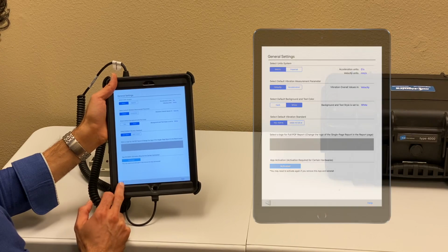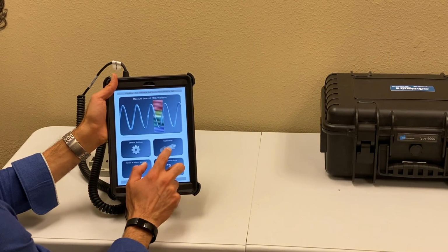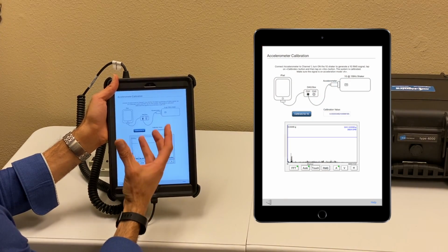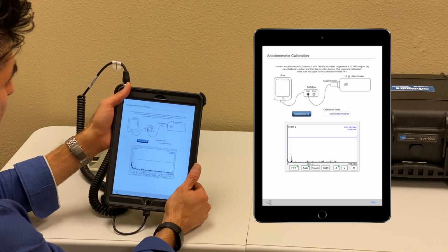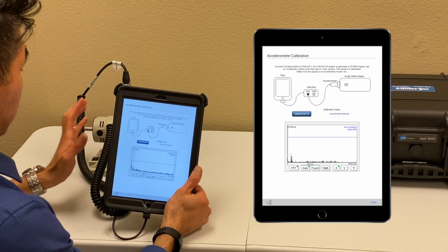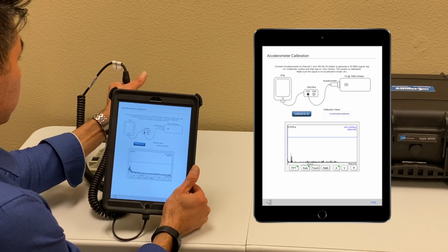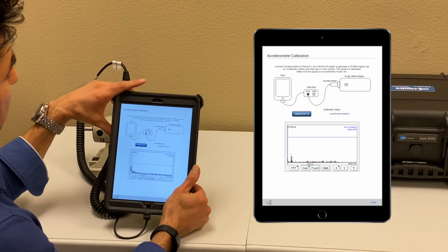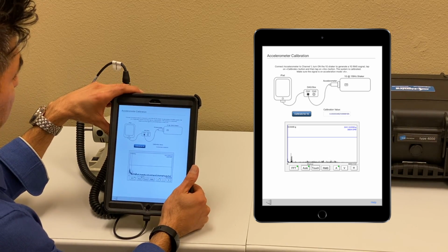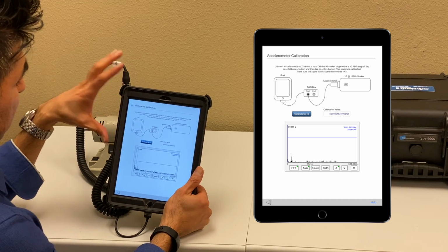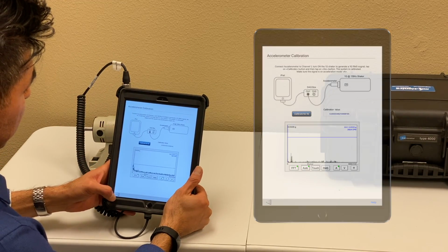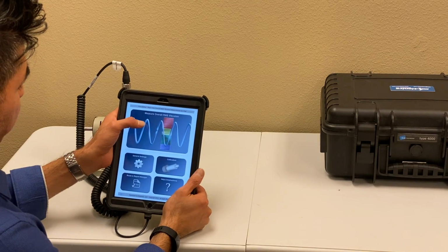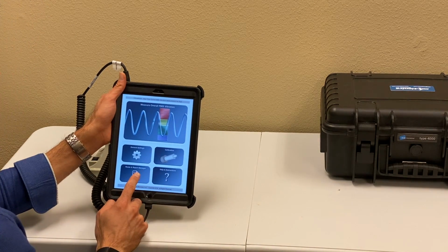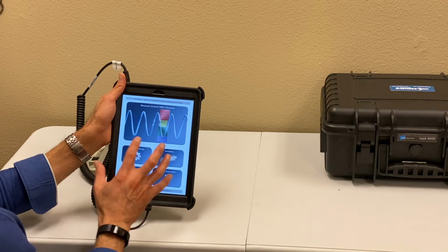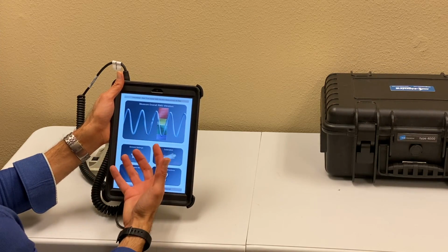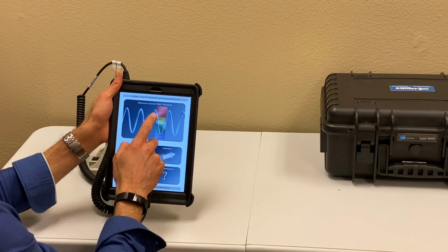Let's go back to the main menu, and the calibration part. You should make sure the system is calibrated. You come here and connect your accelerometer to a 1G standard shaker and calibrate. Make sure the system is calibrated. This system is already calibrated. And the report manager has a database that I'll show you, and we'll see how you can access your reports once you save them.